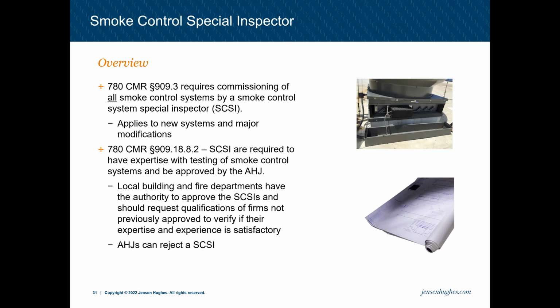So these tend to be things that require inspection throughout, and not just a test at the end, or like a 30% construction review and a test at the end. The smoke control special inspector is also not the engineer of record, and does not need to be the engineer of record. The special inspector can't be the installer, for obvious reasons, but the special inspector is there to ensure that the system was built in accordance with the design documents.